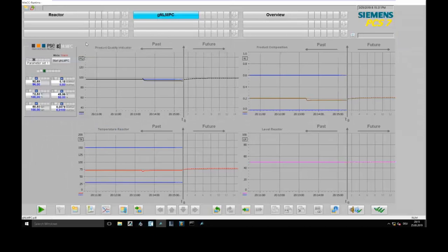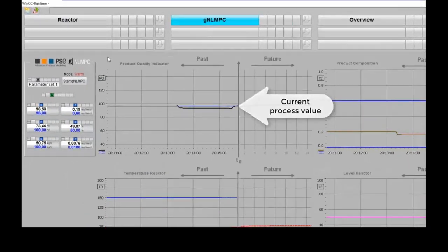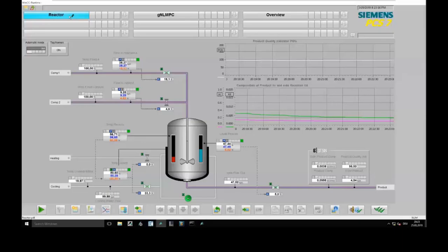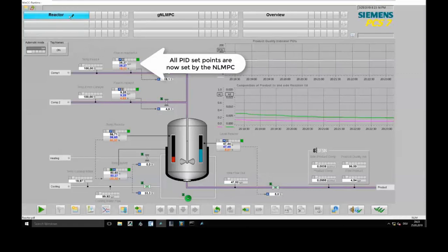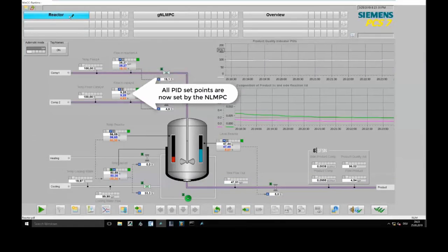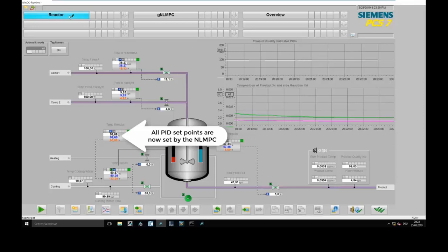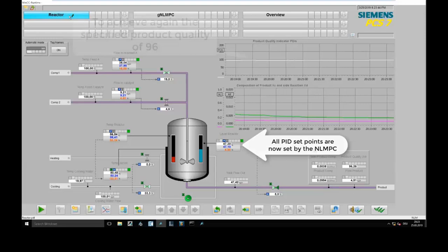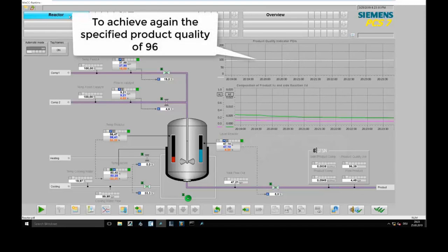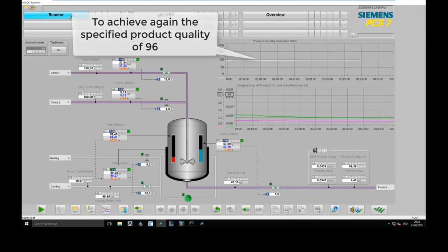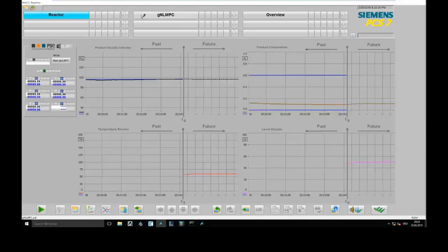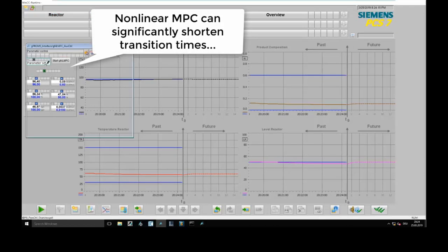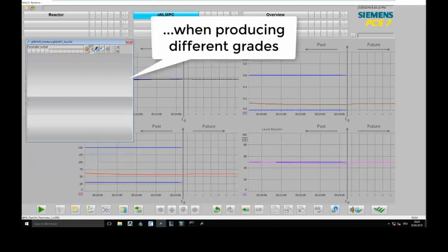PIDs cannot compensate for that because the disturbance cannot be monitored. By switching on the model predictive control, which is able to detect this change, we can compensate the error quickly. The model predictive control then sets the set points of all PIDs automatically. This is quite important for the next showcase: grade changes. When changing the grade of the polymer, we change the set point of the key performance indicators — like melt flow index — directly.